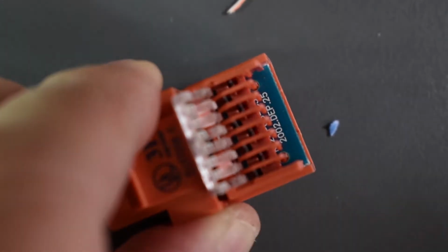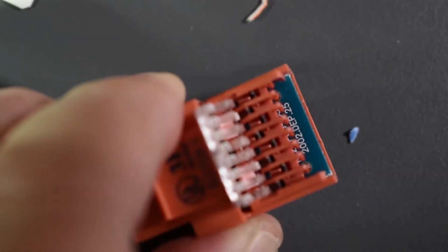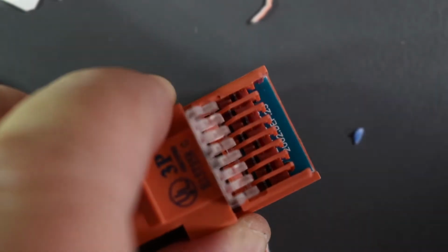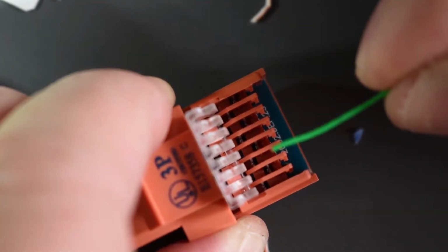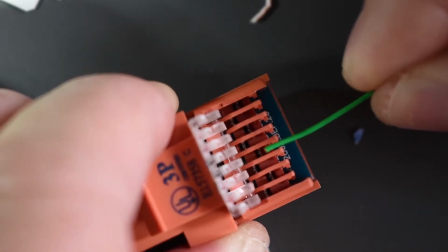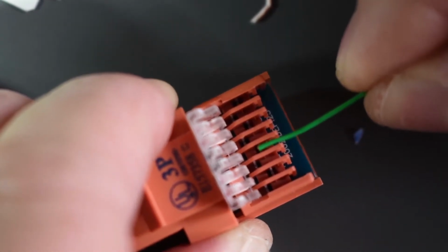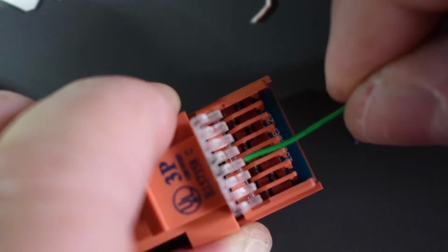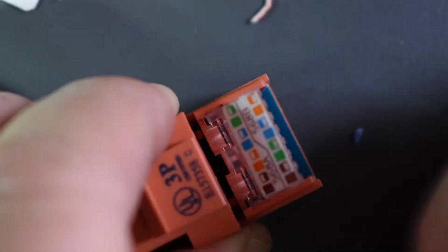All right. So now, when we put the conductor in, we have to make sure that we go past the connector. So let's say if I put one here just like that, it is going to reach the connector right here, and the punch down, the connection, is going to be made once we come down with the hinge.